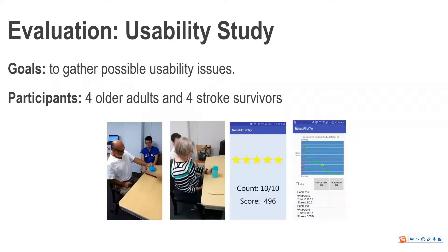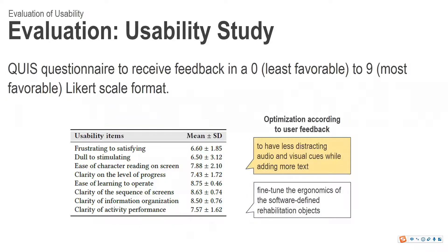In the usability study, the goal is to gather possible usability issues. We enrolled four older healthy adults and four stroke survivors. Each participant was asked to perform all specified activities. Afterward, a questionnaire was delivered to each participant to receive feedback, using a 0 (least favorable) to 9 (most favorable) Likert scale format. We then made optimizations according to user feedback — for example, providing less distracting audio and visual cues while adding more text, and fine-tuning the ergonomics of the software-defined rehabilitation objects.